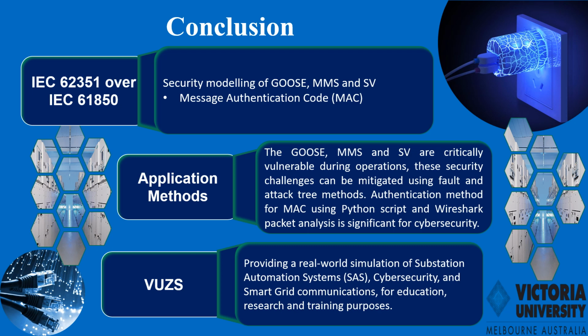The IEC 62351 standard is still in its infancy stage in handling the communication and information security of the IEC 61850 standard protocol. The GOOSE, MMS, and SV are critically vulnerable during transmission and application of messages across the substation. To further address the security challenges, a case study was initiated to illustrate the importance of fault and attack tree methods in effectively mitigating intrusion and detecting event anomalies in the substation. Furthermore, an authentication method for MAC was also proposed, generating a secret key using a Python script which contains data and code. For packet analysis, Wireshark was chosen due to its popularity and capability for various statistical packet analysis in a network.